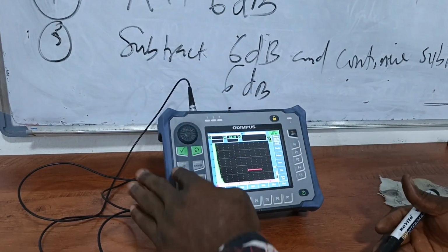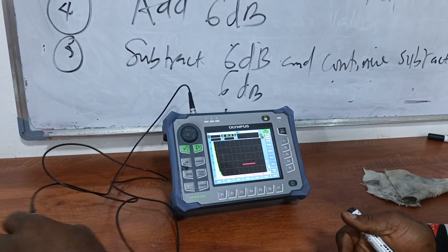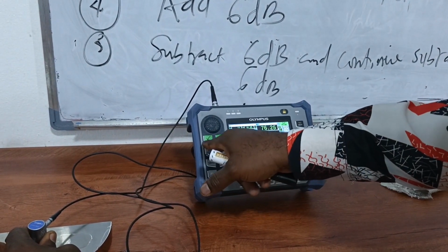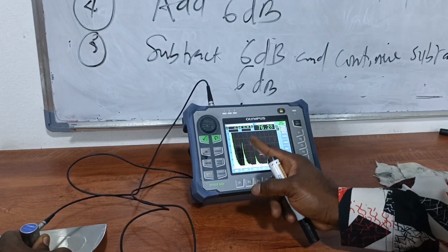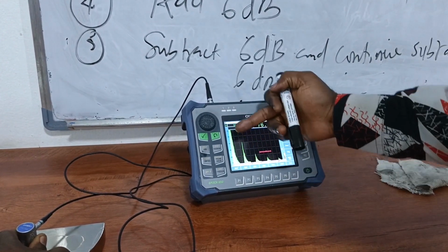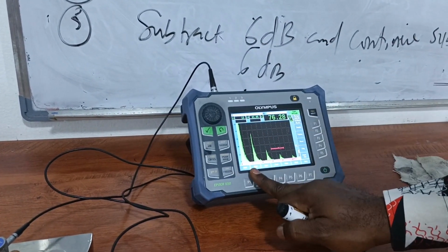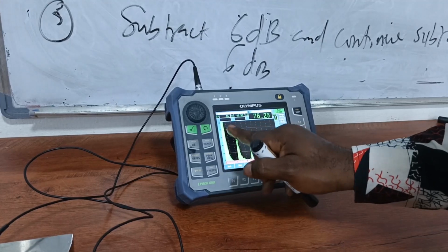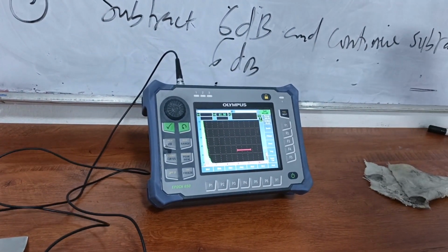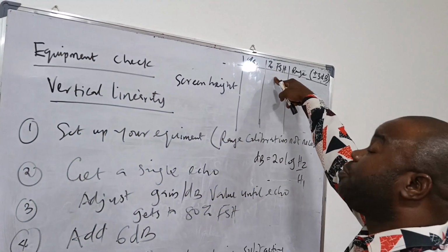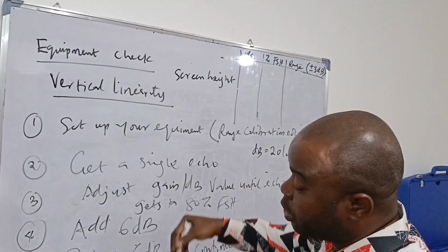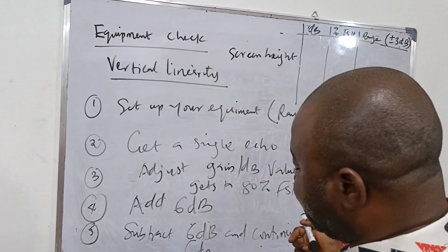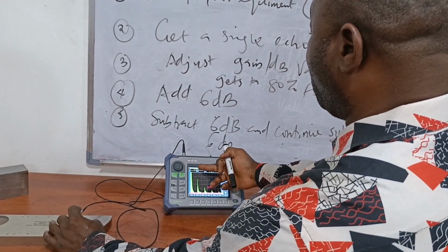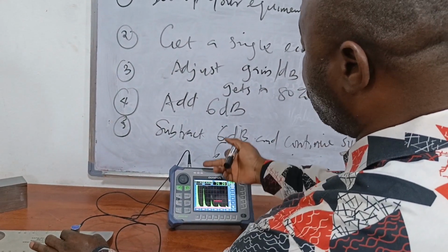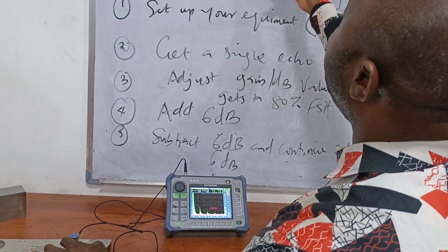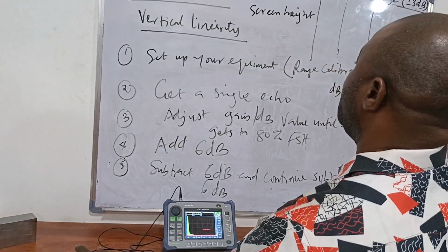Now, there's a relationship between the value of your dB and the height of the echo. So if I'm getting an echo here, if I increase my dB, the echo height should increase. And of course, the echo height is measured based on the percentage of the full screen height. My first echo is almost at 100% of the full screen height. So for every dB value I have, I will have a corresponding percentage full screen height. Seeing whether your echo obeys this dB rule, when you increase or reduce the value of your dB, is what determines whether your vertical linearity is okay.